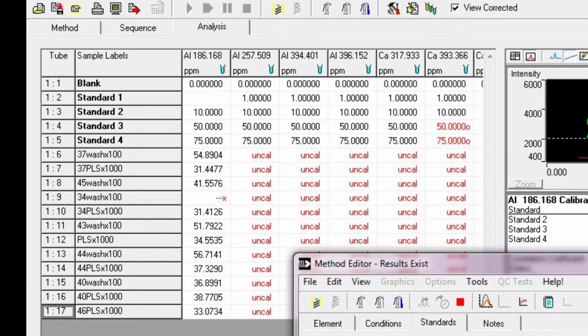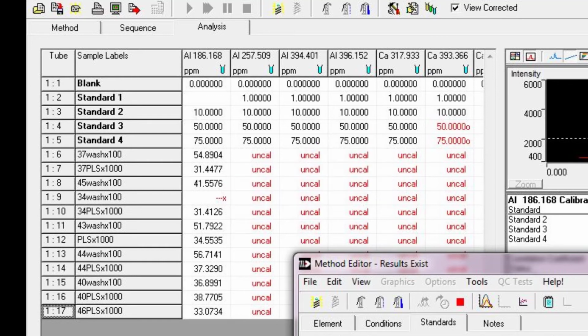You can see here that almost all of the samples for this particular wavelength have been given a concentration value, with the exception of the sample in tube number 9. The "-x" means that the actual value is higher than the maximum value included in the calibration line. In this case, the actual value must be greater than 75 ppm. Sometimes you'll see a "-v" instead of a number, which means that the actual value is below the lowest concentration standard. And a small negative number in red is the system's attempt to calculate a value that is close to, but still below, the lowest standard used in the calibration line. In most cases, the value should be 0, but is a little off because of the calibration line calculation.